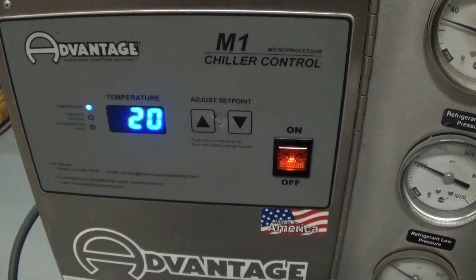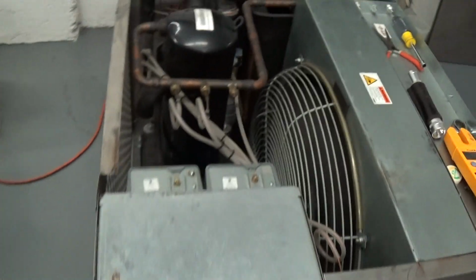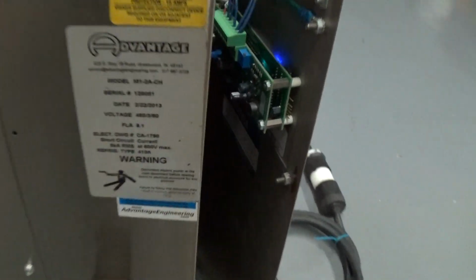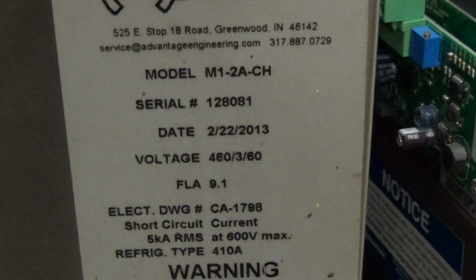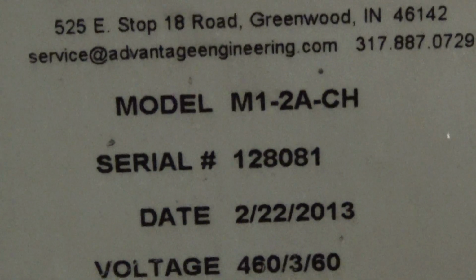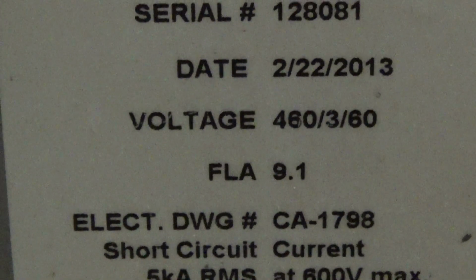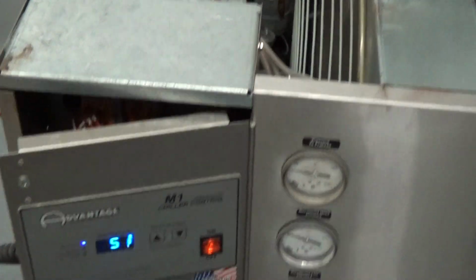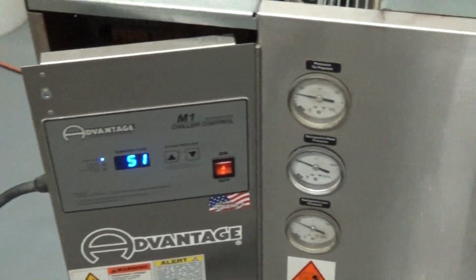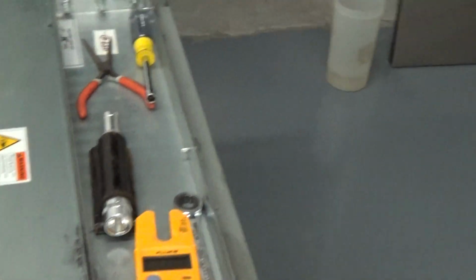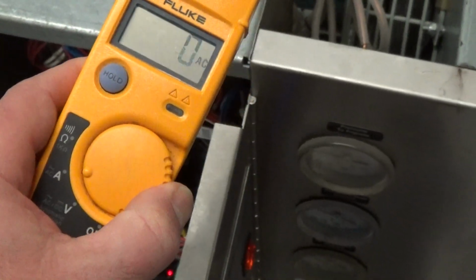As you can see, it's already turned on. This is a 460 volt three-phase unit. In the world of chillers, I'm very close to the unit, but it's pretty damn quiet, frankly. 9.1 amps is the tag rating for load. Now this back room today is probably about 58 degrees ambient. In a hotter ambient environment, it'll draw more amps. Let's see, I'm gonna guess it's gonna be in the 6 range or something.